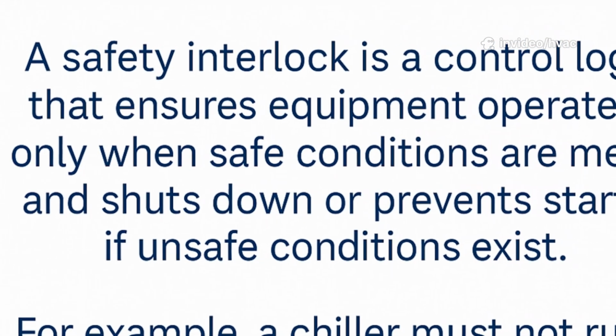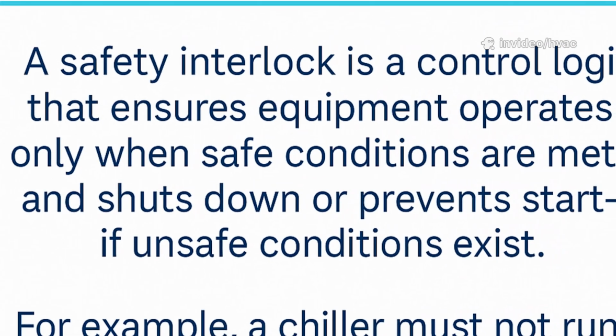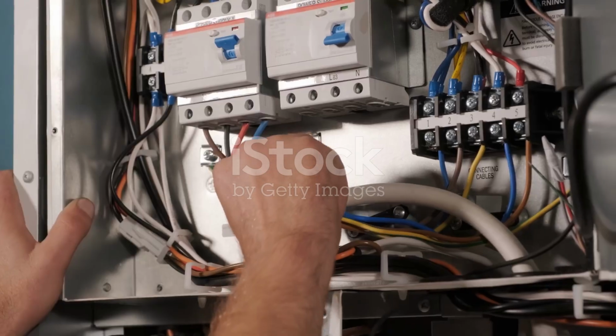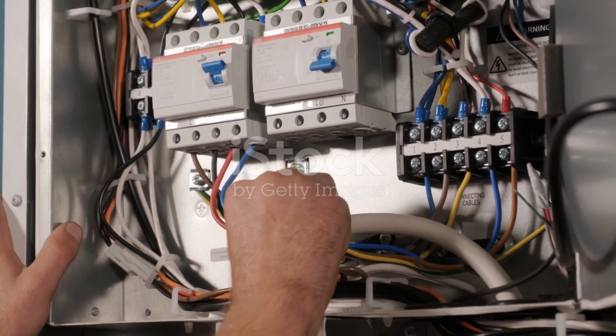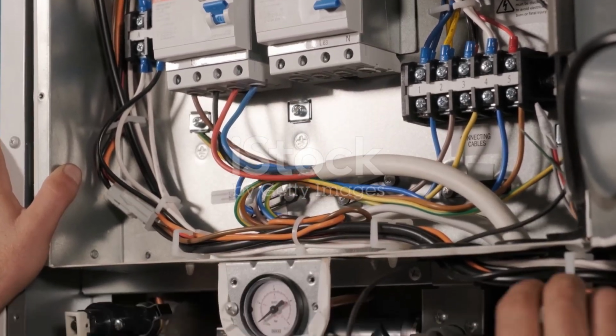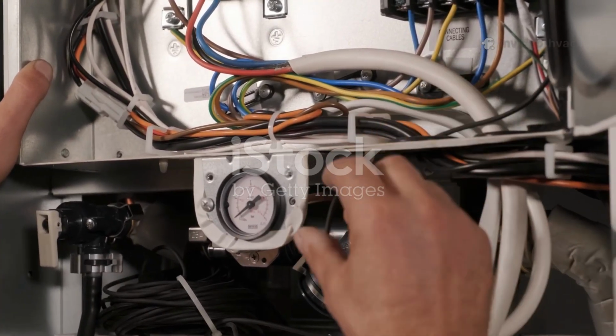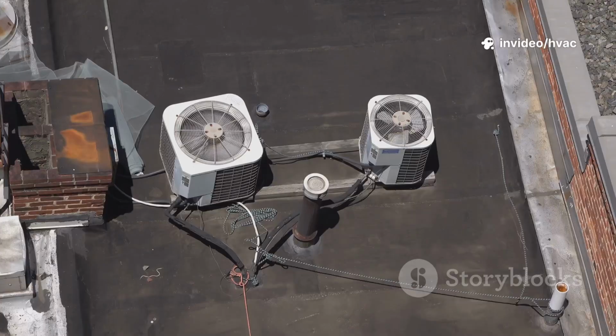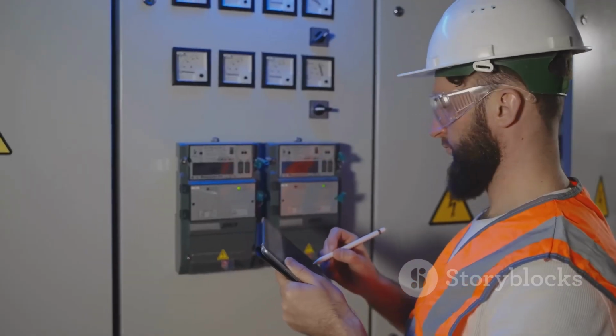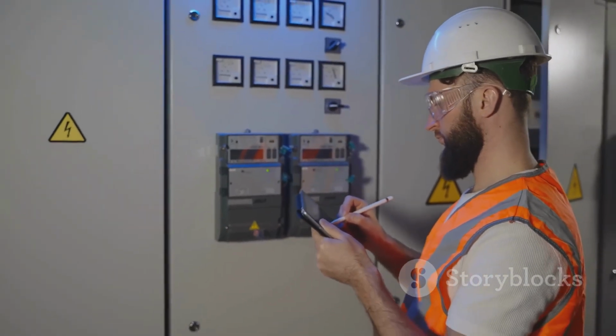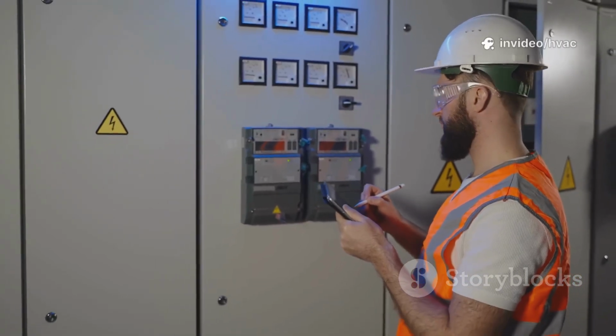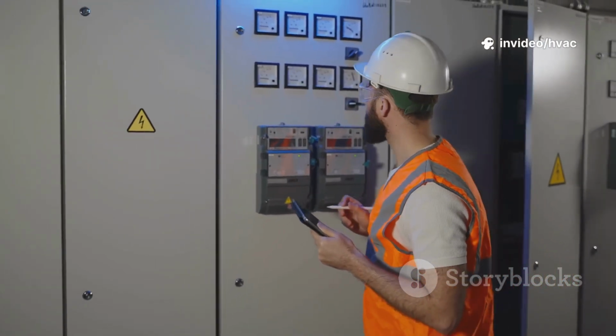What's a safety interlock? In the world of mechanical and electrical systems, especially HVAC, it's a term you'll hear all the time, because safety is always the top priority. But what does it really mean, and how do we design it to work reliably? A safety interlock is a feature that links two or more pieces of equipment together, making the operation of one device completely dependent on the status of another. This connection ensures that machines only run when it's absolutely safe to do so, preventing accidents and equipment damage.